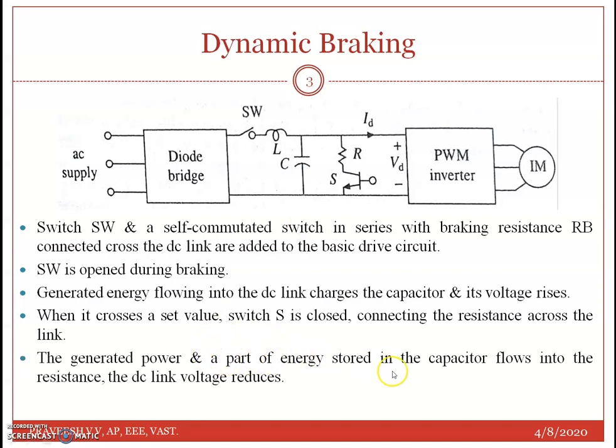A part of energy stored in the capacitor flows into the resistance and the DC link voltage reduces. By closing and opening switch S based on the value of DC link voltage, the generated energy is dissipated in the resistance, giving dynamic braking.